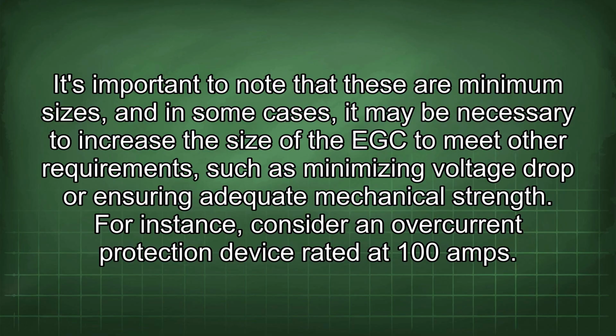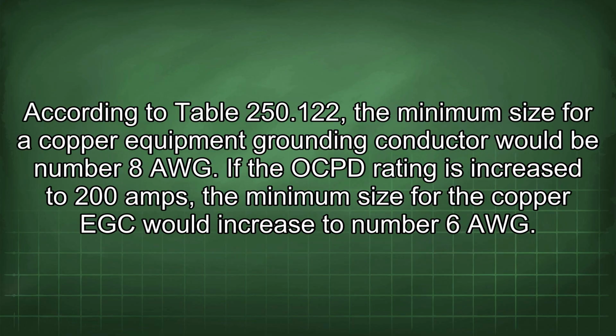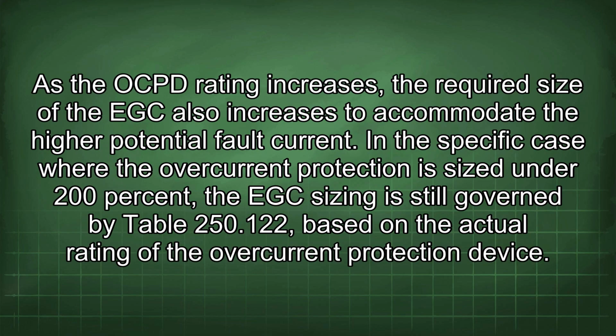For instance, consider an overcurrent protection device rated at 100 amps. According to Table 250.122, the minimum size for a copper equipment grounding conductor would be number 8 AWG. If the OCPD rating is increased to 200 amps, the minimum size for the copper EGC would increase to number 6 AWG. As the OCPD rating increases, the required size of the EGC also increases to accommodate the higher potential fault current.